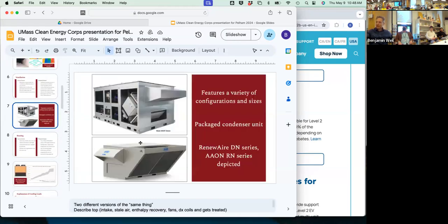Yeah, so one benefit here is these units are unitary. They get craned onto your roof. The heat pump, all the refrigerant, everything is all part of one object. And so you don't have refrigerant to your building. In the case of the gym unit, you do have a hot water coil going to it, but that's really only to supplement.